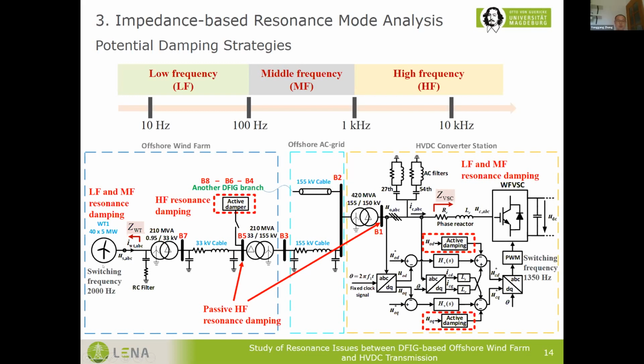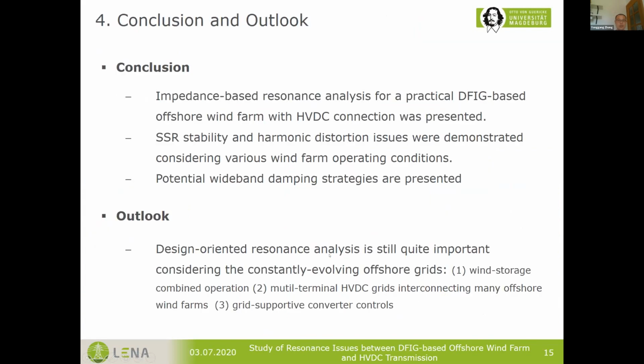However, due to the restrictions of their switching frequencies, only the low and middle frequency resonances can be effectively damped. And two possible choices for damping the high frequency resonances can be installing active dampers with higher switching frequency or passive dampers. The choice of the damping strategy may depend on the overall evaluation of the performance and the cost.